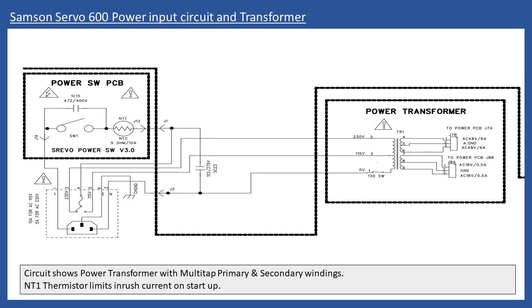So imagine you had to change the fuse for a particular reason. You can't even see, there is no correct orientation, shall we say. There's nothing shown on there. And I've had amplifiers which have been brand new, shipped from factory, come into the workshop under warranty saying it's blowing the mains fuse. And what it is, for whatever reason that fuse holder has been removed and it's been rotated, the fuse replaced, put back in, and what's happened is the 115 volt winding has been selected. Alright, so when you are working on power transformers, just be aware of that.